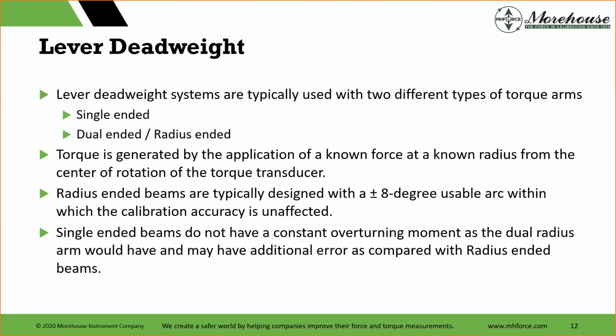Single-ended beams do not have a constant overturning moment as the dual radius arm would have, and may have additional error compared to radius-ended beams. We see a lot of single-ended beams. In fact, so much that when we teach this class, now and then, we take down a single-ended beam, and we have known weights, and we can show there's a significant error source when you compare single to dual. Single-ended are much less accurate and carry a much higher uncertainty. So when we do that type of demonstration, you get to see it, and it's quite large. So if you're in the market looking for arms, I always recommend dual-ended.